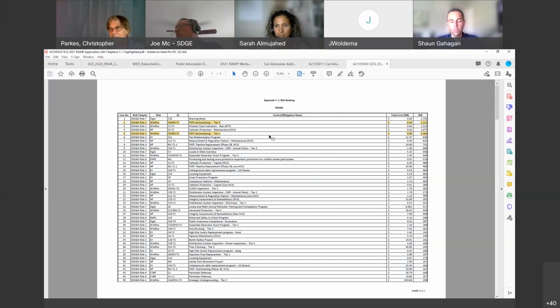We had a really good example: a particular area of our service territory, on one circuit, called Hellhole Canyon, experiences very high winds. Previously, the sectionalizing device was located such that de-energizing Hellhole Canyon meant de-energizing other customers further back too. By installing a sectionalizing device closer to that park area, we can now de-energize only about 30 customers right where the most extreme wind occurs during a PSPS event, leaving the rest of the circuit energized. That's how we scoped these projects and determined why we use number of sectionalizing devices installed as the unit.